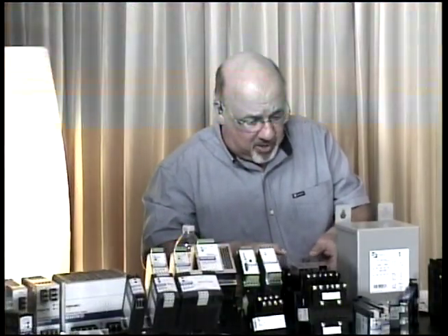These are going to be primarily used in industrial control type situations where your incoming factory or your plant power is going to be three-phase, 480, 240, and you're going to have different control enclosures throughout your plant, with everything from motor starter circuitry to control panels with PLCs and sensors and full automation. So you're going to use these primarily to bring that incoming voltage and step it down to a control voltage. And in most instances, that's going to be 120 volts AC.